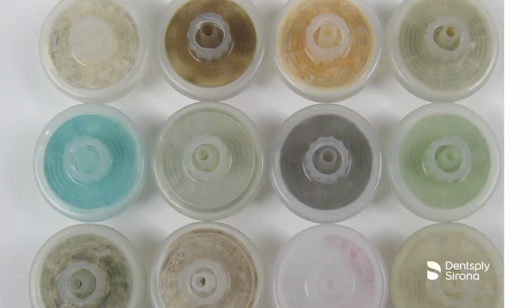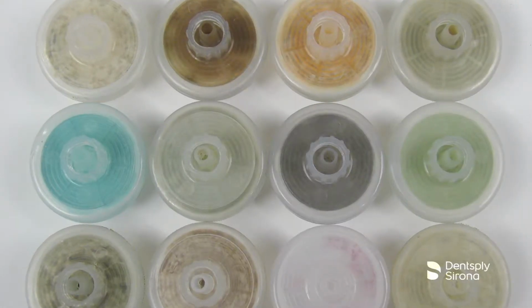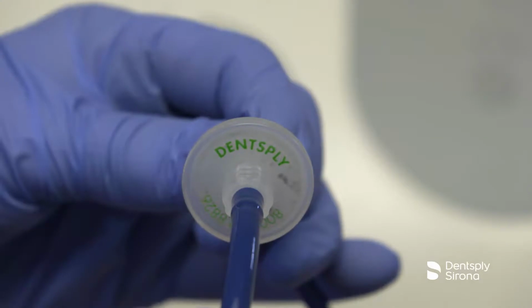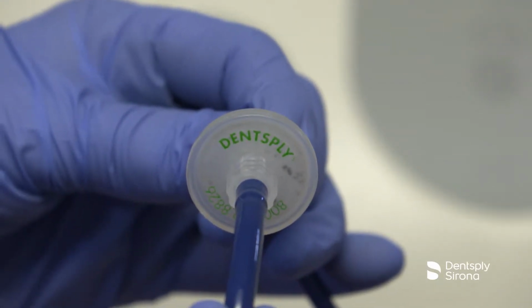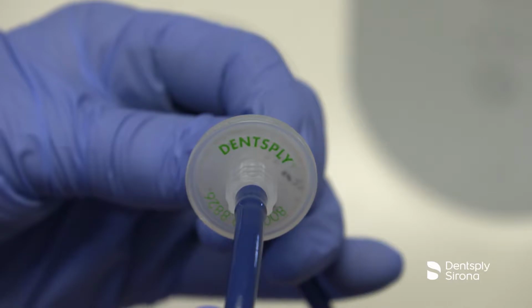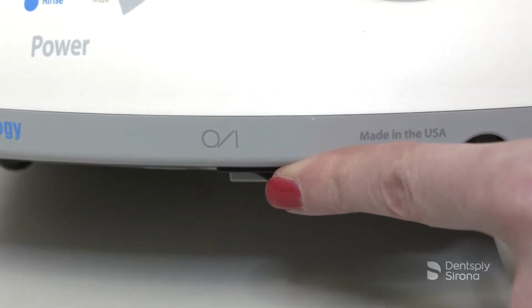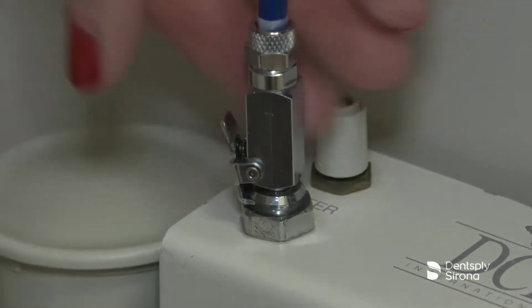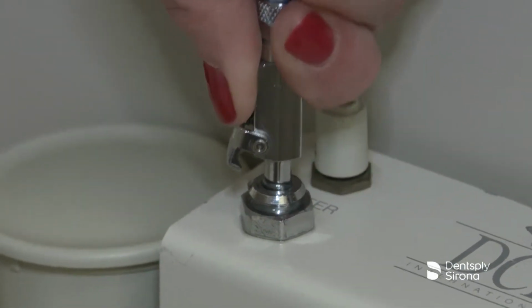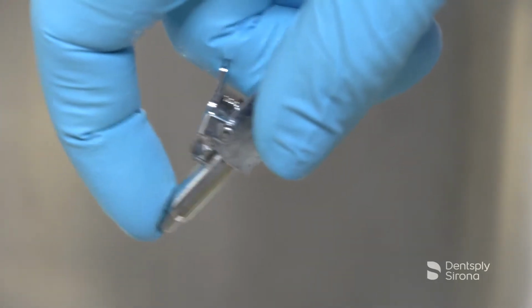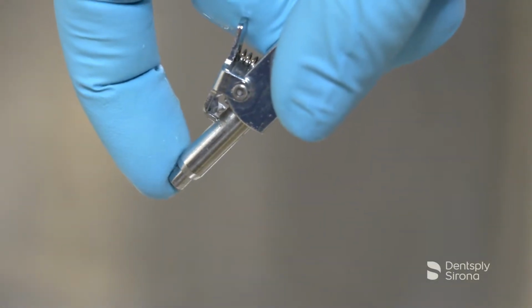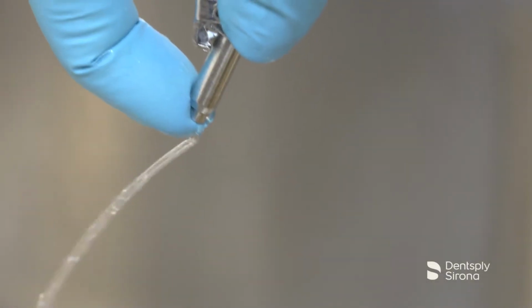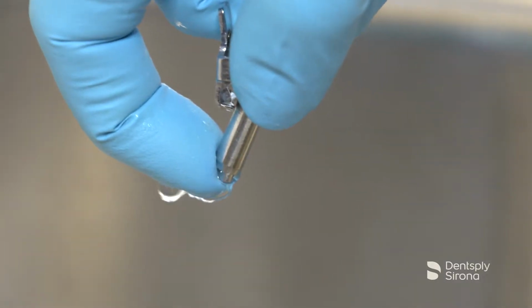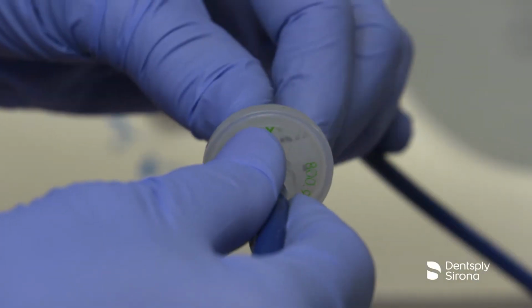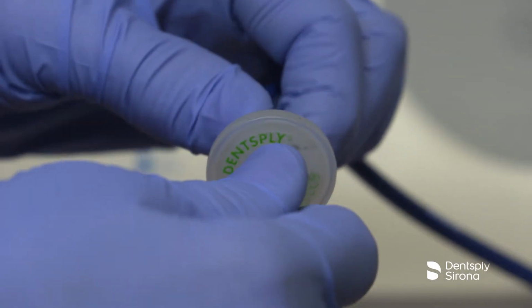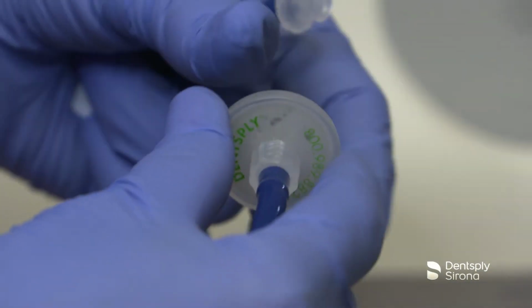When the waterline filter becomes discolored, the filter should be replaced to prevent reduced water flow to the Cavitron Plus system. This should be checked and/or replaced monthly. To change the water filter, begin by verifying that the system is turned off. Disconnect the water supply hose from the dental office water supply. If a quick disconnect connector is attached to the end of the hose, relieve the water pressure by pressing the tip of the connector in an appropriate container and drain the water. Grasp the fittings on either side of the filter disc and twist counterclockwise. Remove the filter section from either side of the water hose.